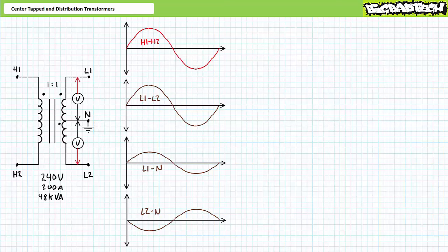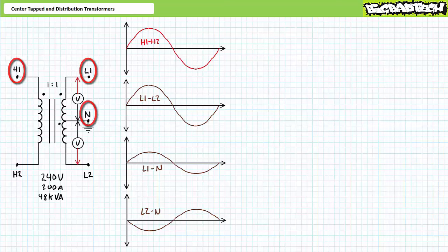Importantly, ground referencing the center tap does not change the location of the phase dots. When H1 is higher or more positive than H2, L1 is higher or more positive than N, and N is higher or more positive than L2. This also means L2 is lower or more negative than N.